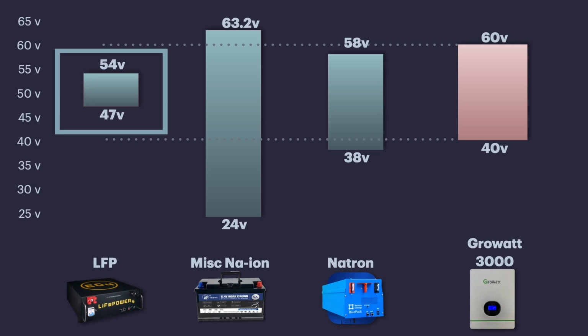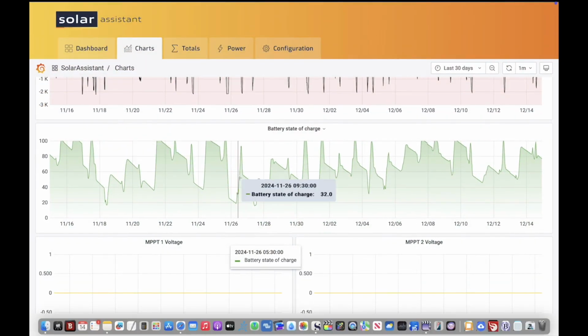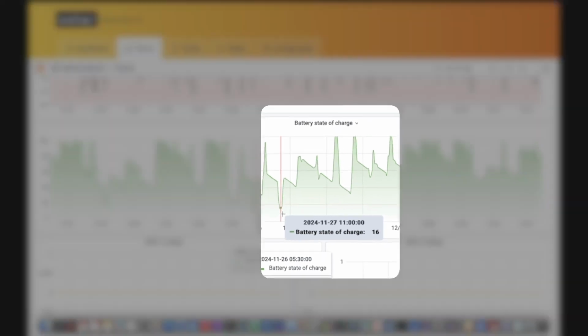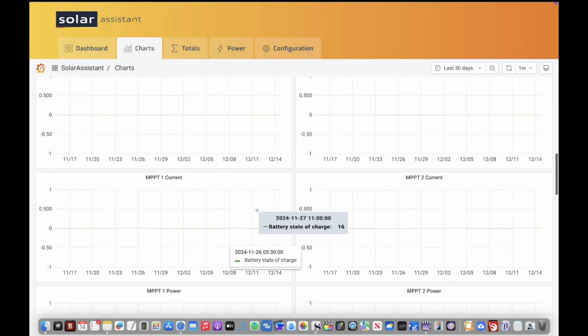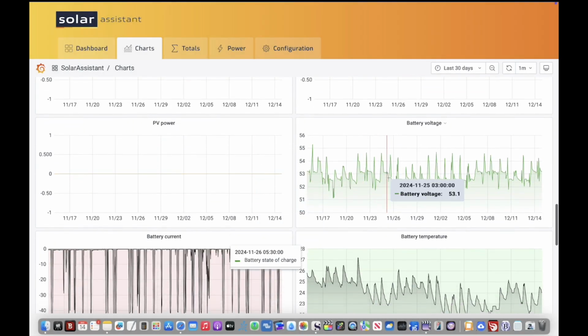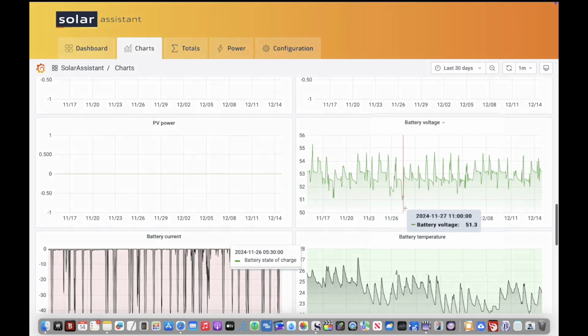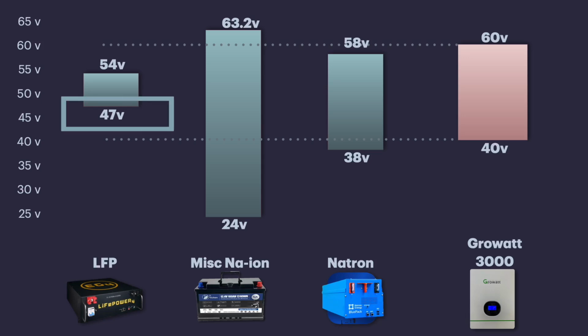You would not normally get down to this lower range of 47 volts. Here is the battery state of charge for the last 30 days in my Growatt system with my G4s. Right here is the lowest state of charge I hit, at 16% state of charge, on November 27th at 11 o'clock. Let's look at the battery voltage for that same time, and you can see I'm at about 51 volts. That's a long way from 47 volts, and this is at 16% state of charge.